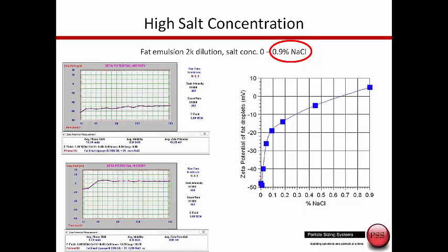If the sample is to be injected into humans, lots of people want to do these measurements at high salt concentration. The dip cell is a better way to do that because the salt doesn't build up on the electrodes, they're easier to clean, and much less expensive to perform these kinds of measurements.